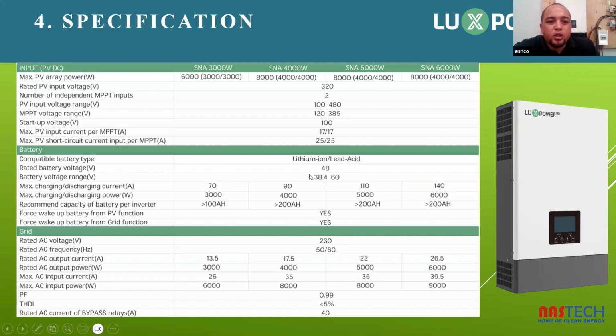The rated battery input voltage that it can take is 48 volts. It has a battery voltage of 38 to 60 volts. The maximum charging is 110 amps. This 110 amps is related to the 60 volt DC. So the power that we get in the end is 5 kilowatt.